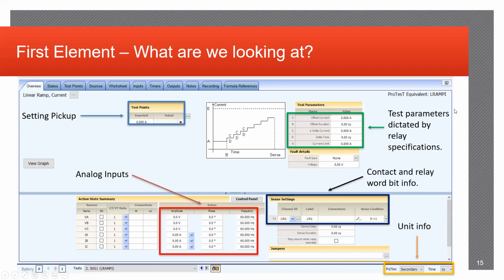Your test parameters are usually identified, again, utilizing the relay manual, which is extremely important because it will inform you of what the parameters should be for your offset current, any limits that may be needed on the relay itself, et cetera, basically all the relay specs that you should be identifying before starting your test. In the red box over here, you've got your analog inputs. This will be all your voltage and current values that you're going to be implementing. Usually you will be using your nominal voltage and currents other than your action current, which we'll go over later.